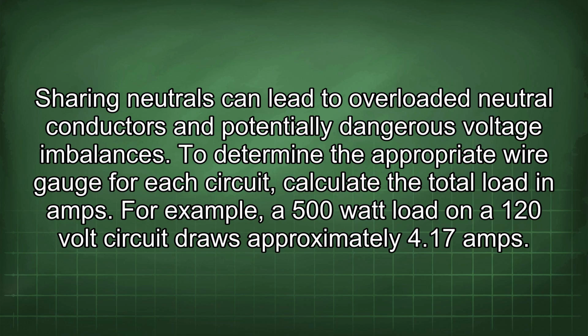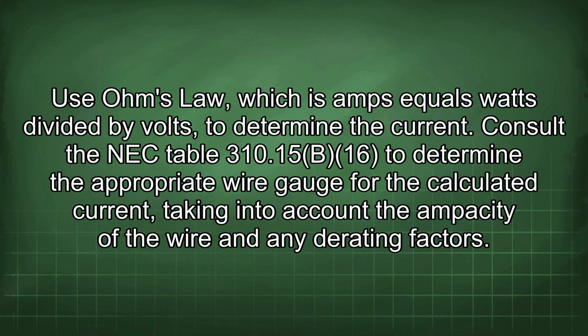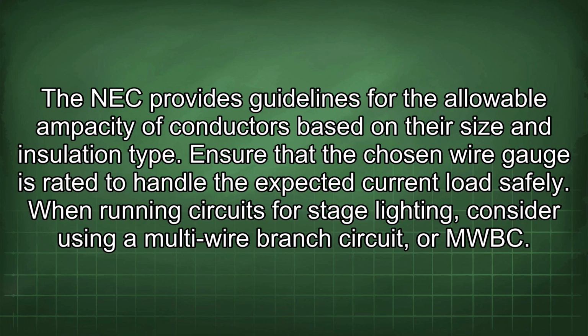To determine the appropriate wire gauge for each circuit, calculate the total load in amps. For example, a 500 watt load on a 120 volt circuit draws approximately 4.17 amps. Use Ohm's law, which is amps equals watts divided by volts, to determine the current. Consult the NEC table 310.15(B)(16) to determine the appropriate wire gauge for the calculated current, taking into account the ampacity of the wire and any derating factors. The NEC provides guidelines for the allowable ampacity of conductors based on their size and insulation type. Ensure that the chosen wire gauge is rated to handle the expected current load safely.